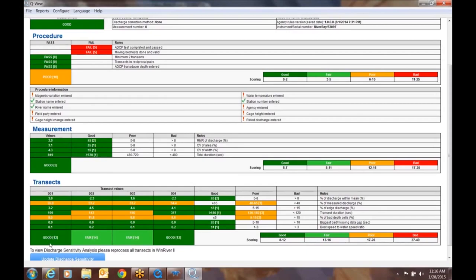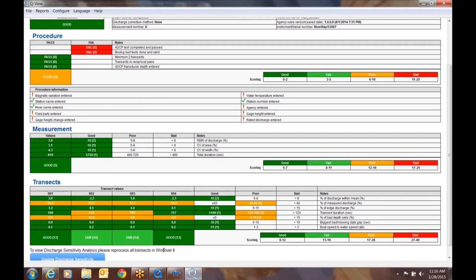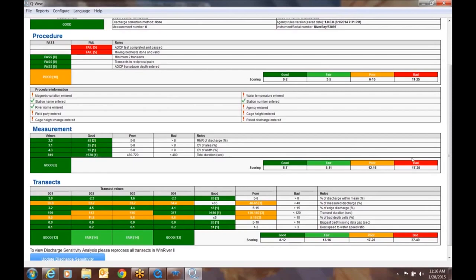So if you look at transect one, transect one had a good measurement. Two and three were rated as fair. Four was good. So all in all, the measurements in the transects themselves are in pretty good shape. We probably could have spent just a little bit longer on transect two and three to bring the rating of this particular measurement a little bit better. I think a little bit more good data. All in all, there's not much you can do to control that, especially if you're using River Rays and RiverPro ADCPs. These devices are doing auto setups. We would expect to have less missing data because of that. So this is a quick snapshot right here of what the data looks like in a post-processing evaluation.